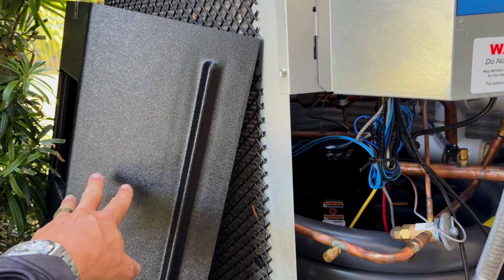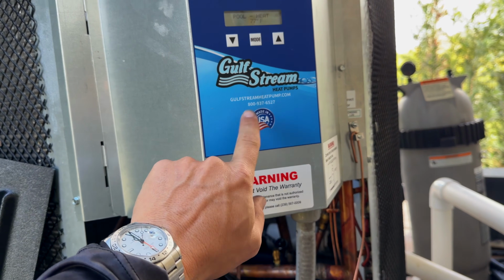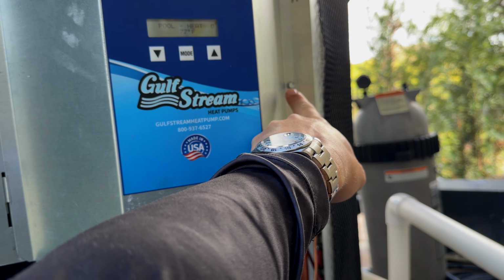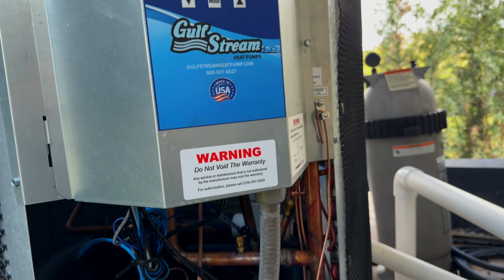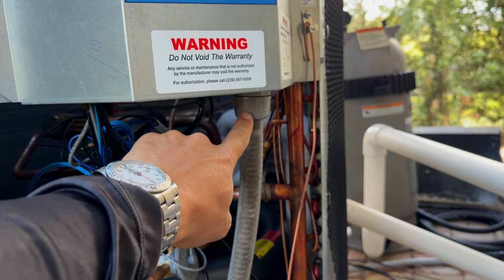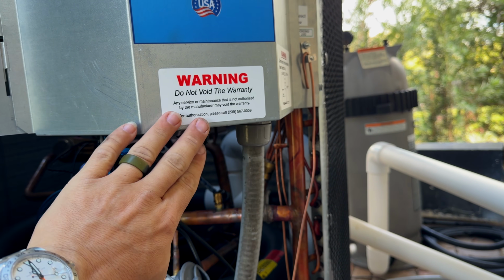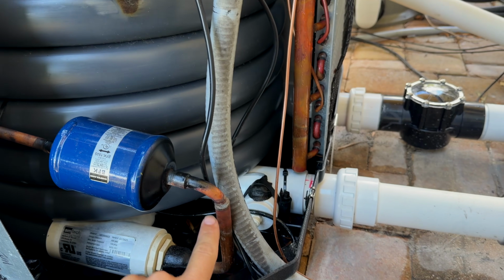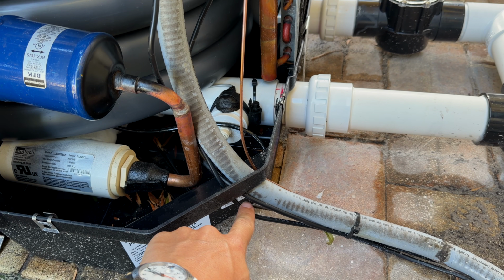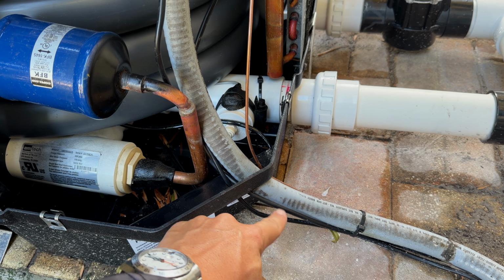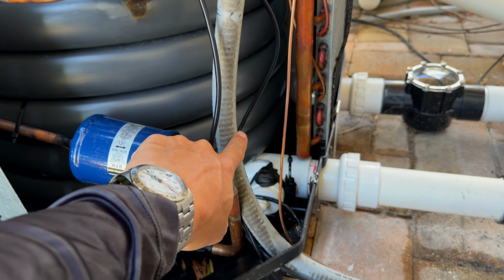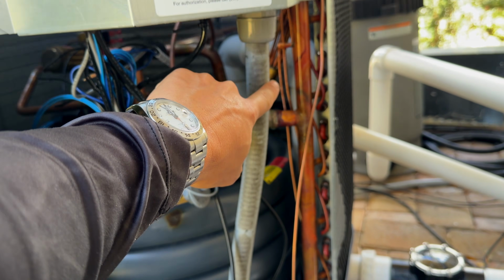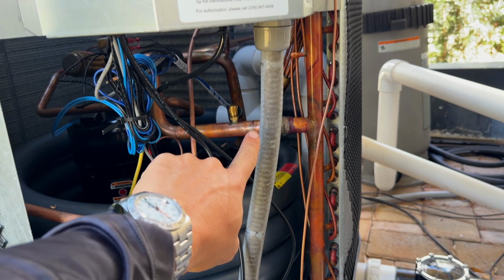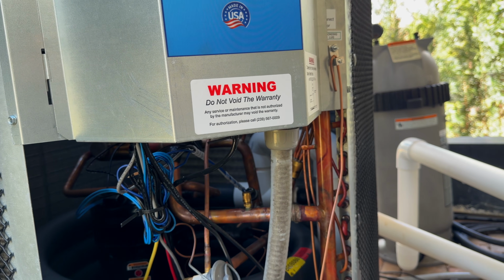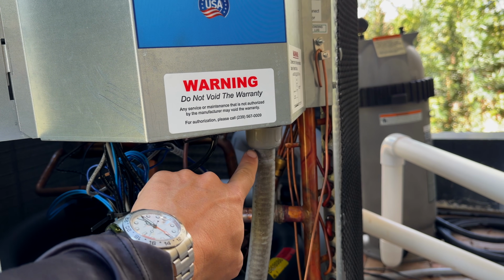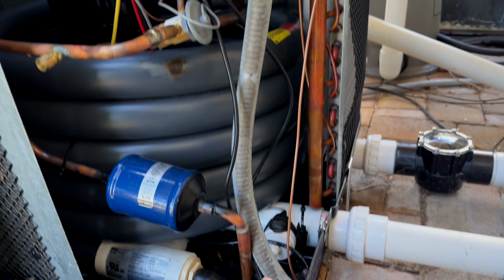So you can see we got the front panel off the heat pump now. All that we need to do to open up this electrical compartment is undo this one screw here, which we'll do shortly. But I want to point out something super important. Notice how this conduit and liquid tight is terminated here at the electrical box. This is the proper way to do it. You don't want - I've seen this time and time again - installers will terminate the conduit right here with a liquid tight or whatever, and then they have literally 50 or 60 amps, 240 volts all running up here, just exposed elements, waiting to have something bad happen. So it's always important to make sure that you terminate this at the electrical box, not down there.